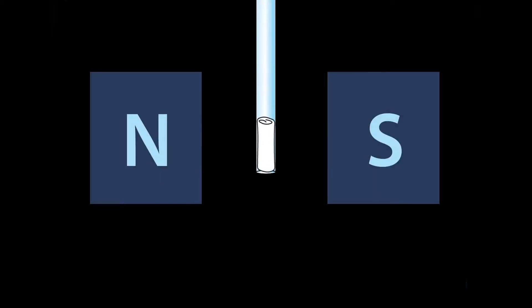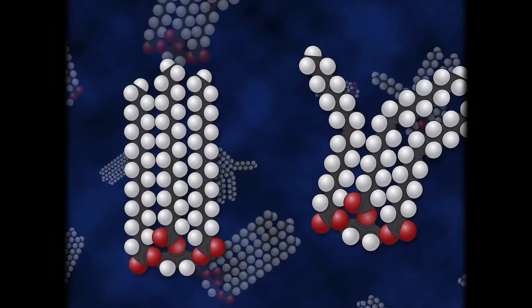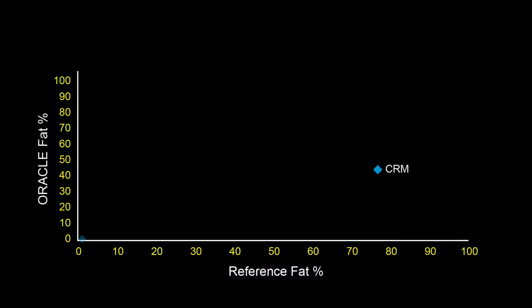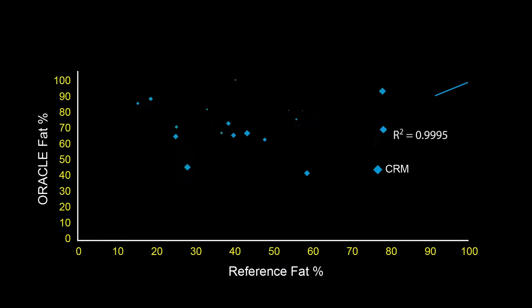The Oracle universal fat analyzer is based on NMR technology, but unlike other NMR fat analyzers on the market that rely on free induction decay or spin echo pulse sequences, the Oracle uses a proprietary pulse sequence that enables fat analysis with no method development and no calibration.